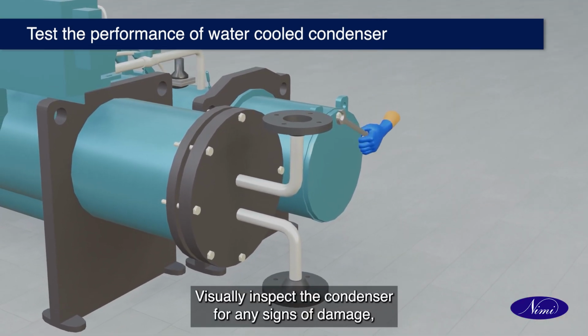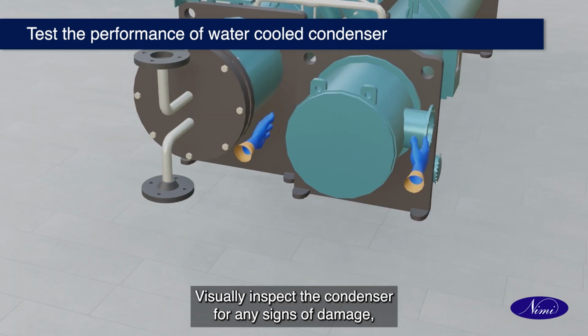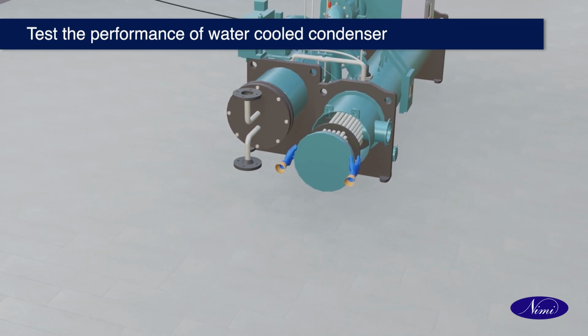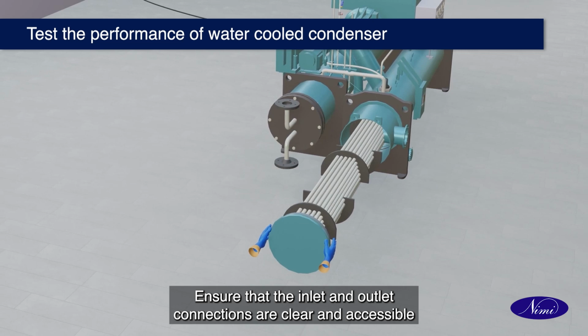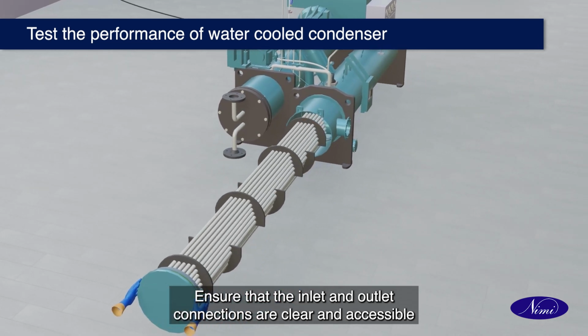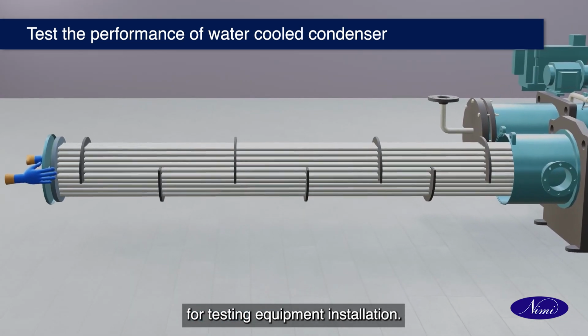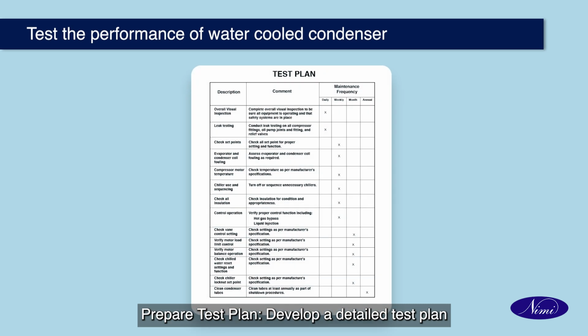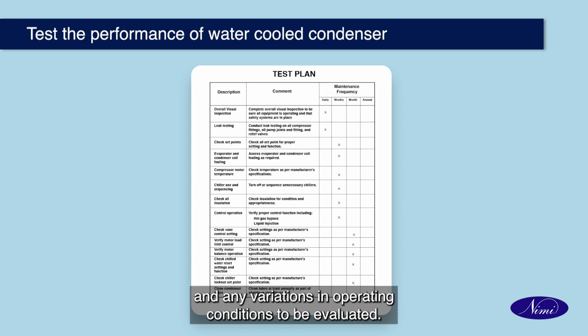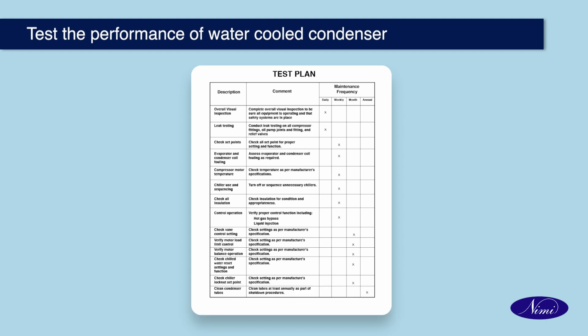Inspect the condenser. Visually inspect the condenser for any signs of damage, corrosion, leaks, or blockages. Ensure that the inlet and outlet connections are clear and accessible for testing equipment installation. Prepare test plan. Develop a detailed test plan outlining the parameters to be measured, testing procedures, and data recording methods. Determine the testing points, duration, and any variation in operating conditions to be evaluated.